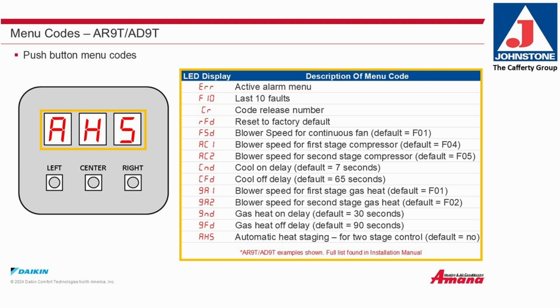AC1, blower speed for first stage compressor cooling, default F04. AC2, blower speed for second stage compressor cooling, default F05. CND, cool on delay, default 7 seconds. CFD, cool off delay, default 65 seconds.